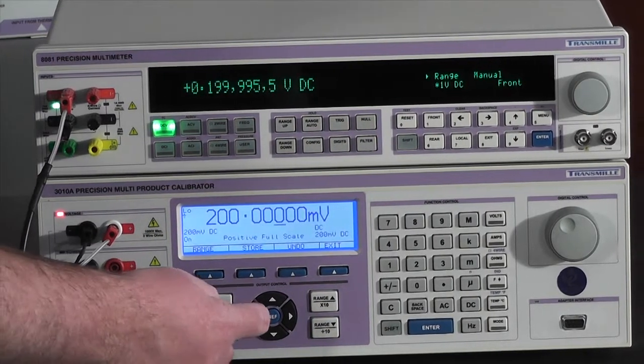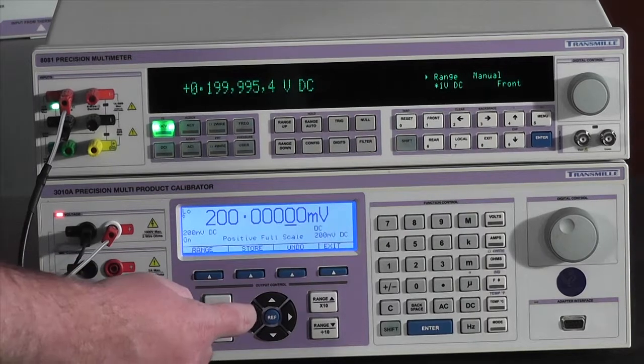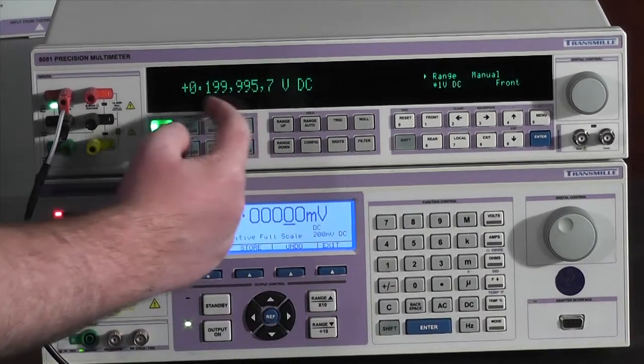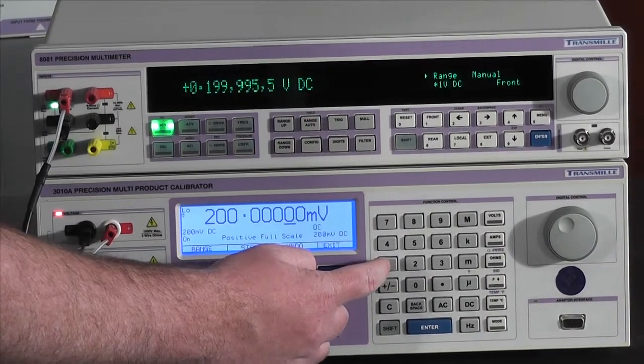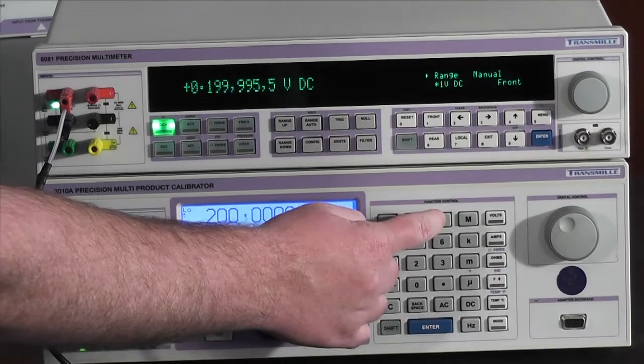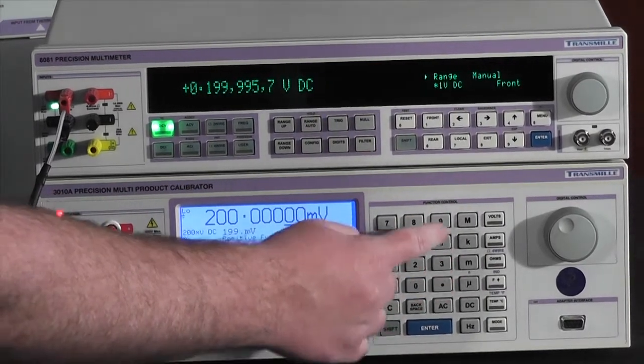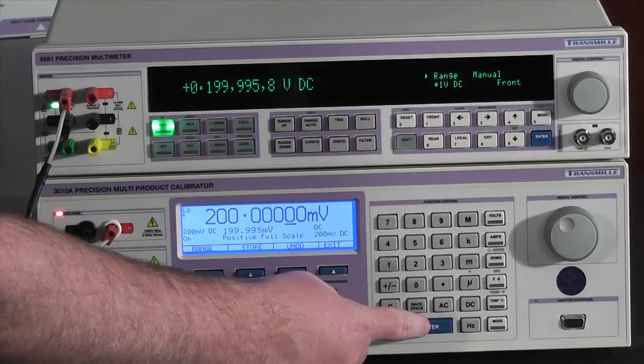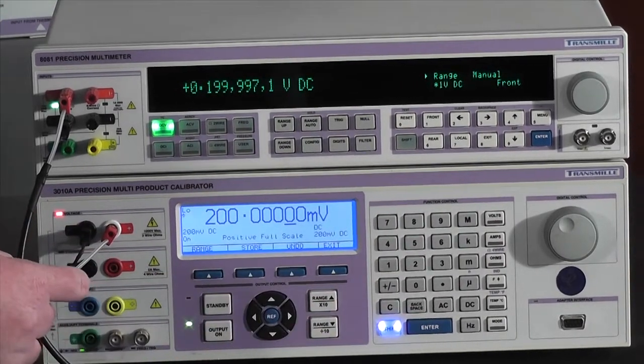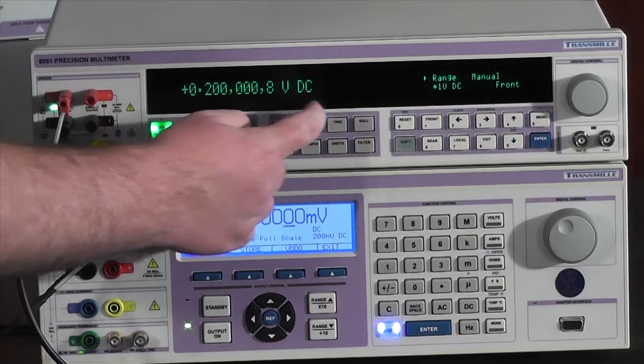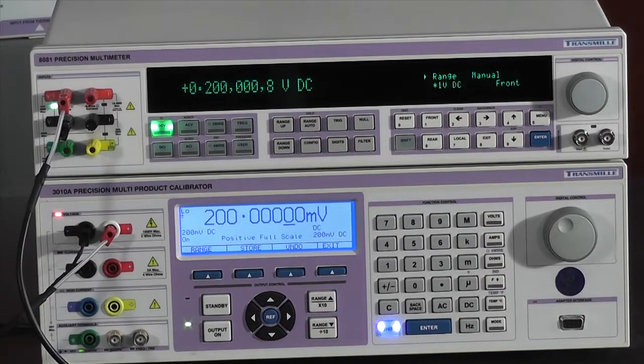Once again, I can adjust this using the cursors or I can directly enter the value that has been measured by the multimeter. So 199.995. Pressing enter will automatically adjust the calibrator to the correct output.